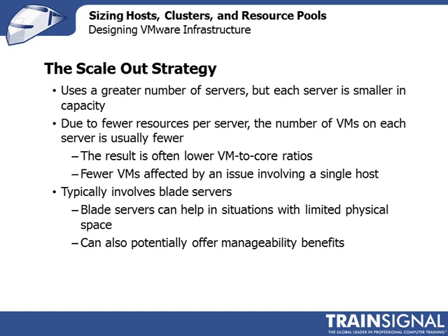Now, typically, this sort of approach is going to involve blade servers or perhaps highly dense rack mount servers. In both of these situations, whether it's blade servers or highly dense rack mount servers, 1U, or perhaps there are some rack mounted options that aren't quite blades but aren't quite typical full width rack mount servers. They're kind of a hybrid of the two. These can help in situations where there are limited physical space. So if you are constrained for rack space, constrained for floor tile space within the data center, and you can address the power and cooling densities that are generated by a large number of servers in a small spot, then this sort of approach might be very beneficial.